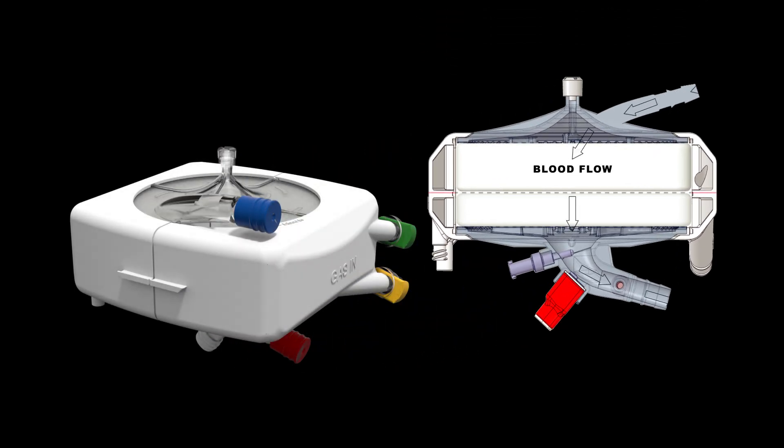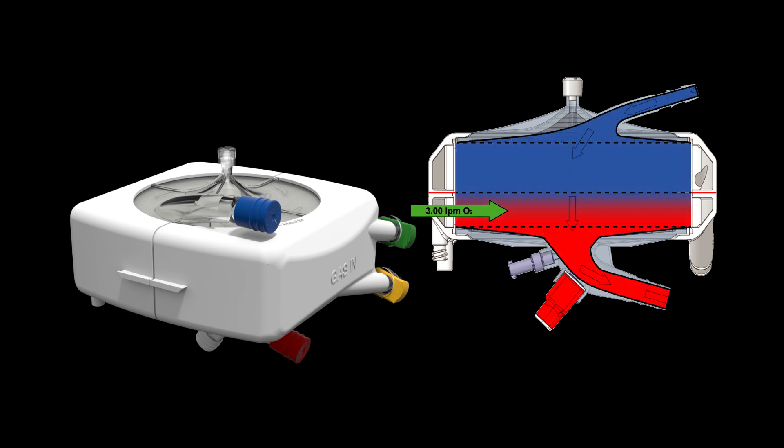The Spectrum Medical Oxygenator divides the hollow fibers into two unequal chambers, each with their own 100% oxygen gas supply. We first ventilate only the fibers in the smaller chamber, which somewhat limits the oxygen transfer due to available surface area. But the small chamber provides adequate surface area to control CO2.